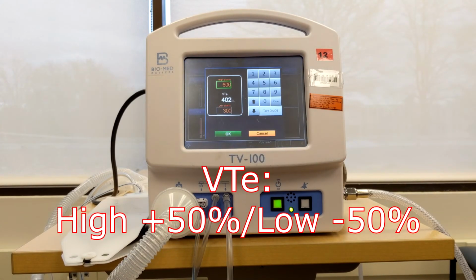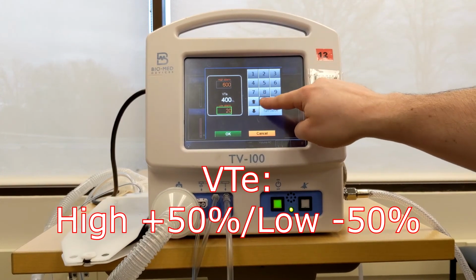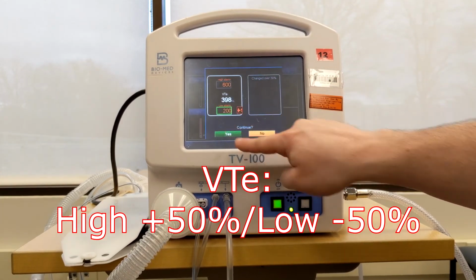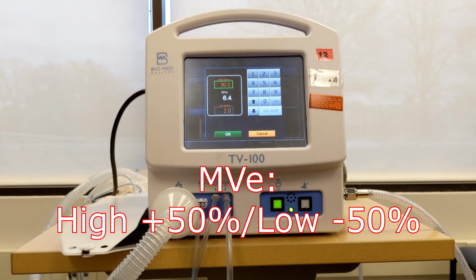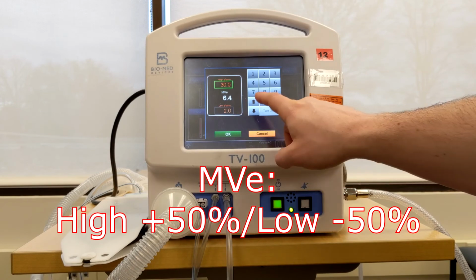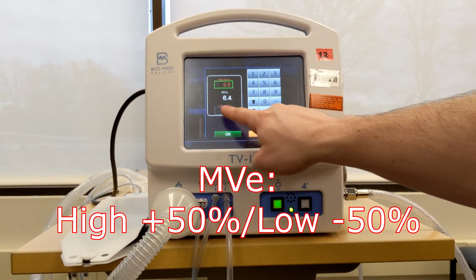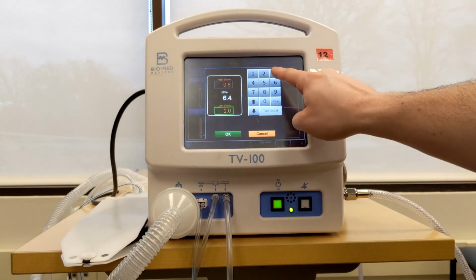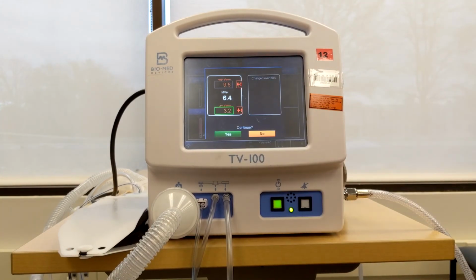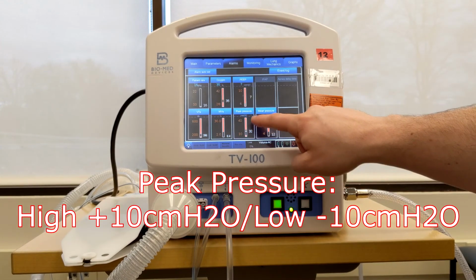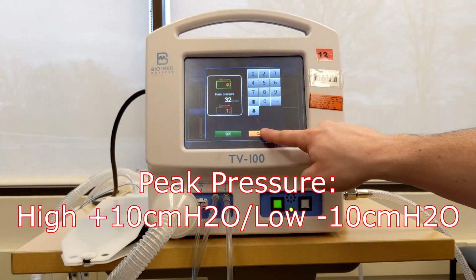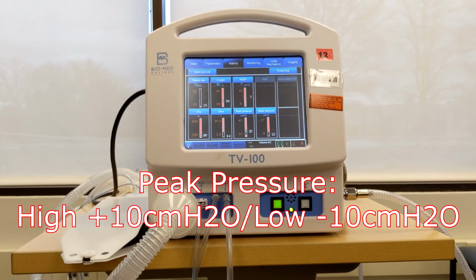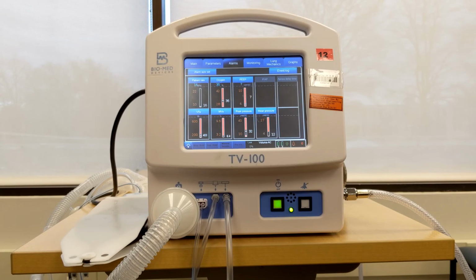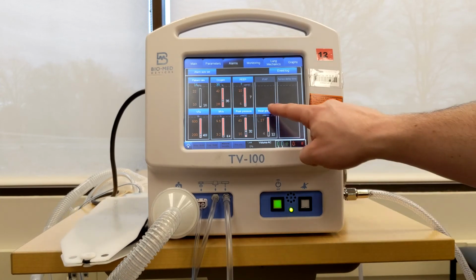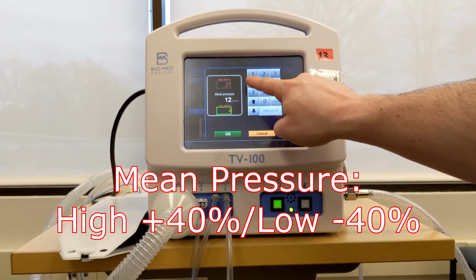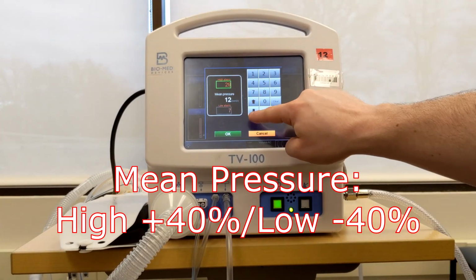Your VTE, or exhaled tidal volume alarm, should be set 50% above and below your average exhaled tidal volume. Your MVE, or exhaled minute volume alarm, will also be set for 50% above and below your average minute volume. Your peak pressure alarm will be 10 centimeters of water pressure above and below PIP, or peak inspiratory pressure. Lastly, your mean pressure alarm will be 40% above and below your mean pressure.